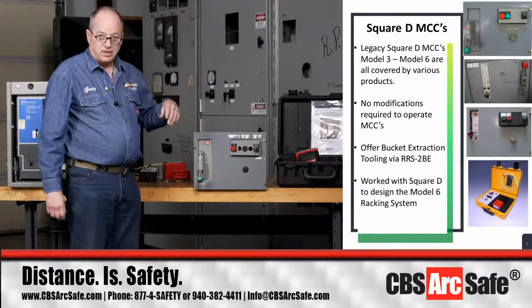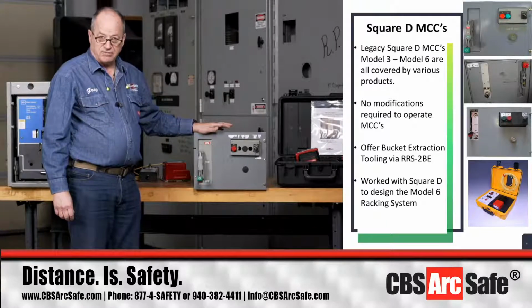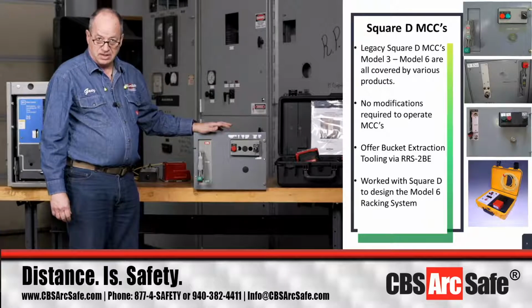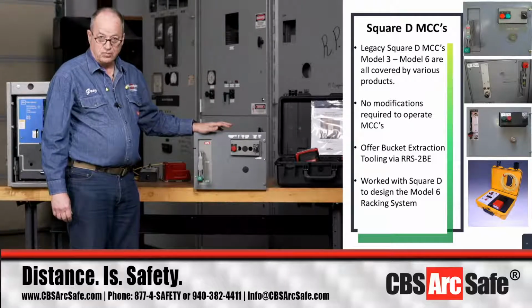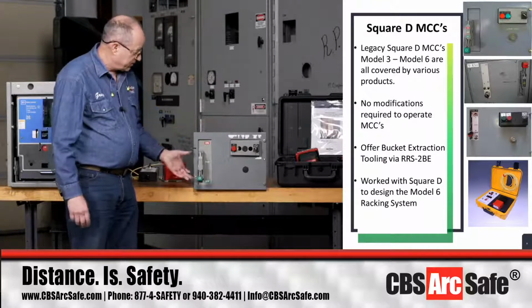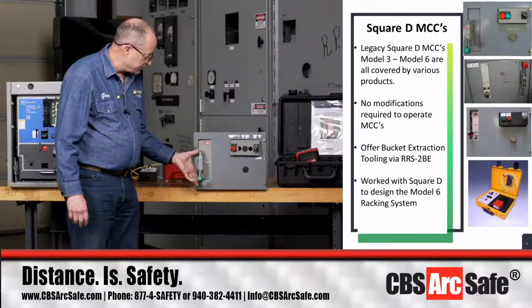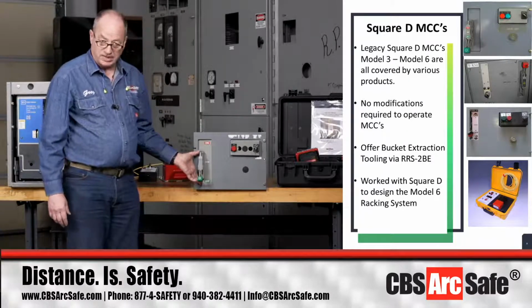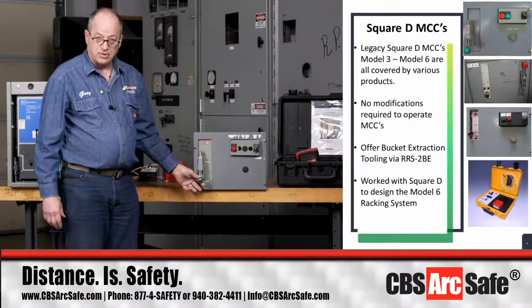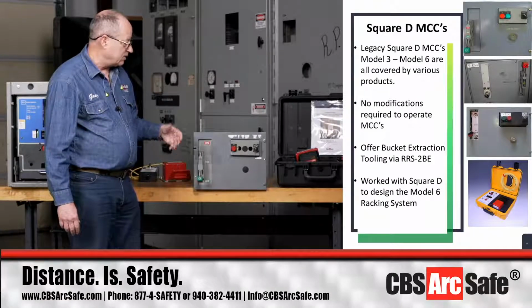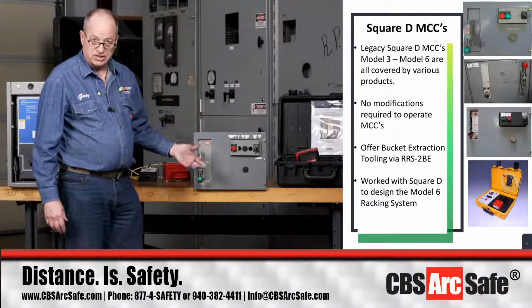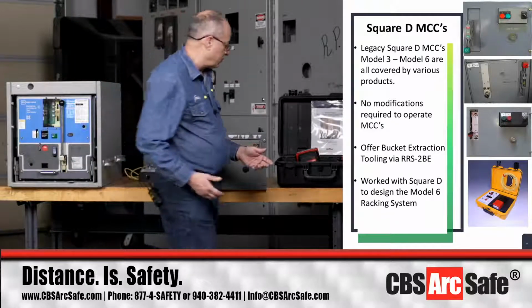So anytime you get a refurbishment bucket, if you've got one of the older ones with large handles and then get a new one, you might wind up needing both of the remote switching kits to perform this operation. Just a heads up, the newer ones are about 3/4 of an inch smaller in overall length, and the handle's a little smaller too. So you have to work with the geometry of what Square D gives you to make a remote switching kit for this system.